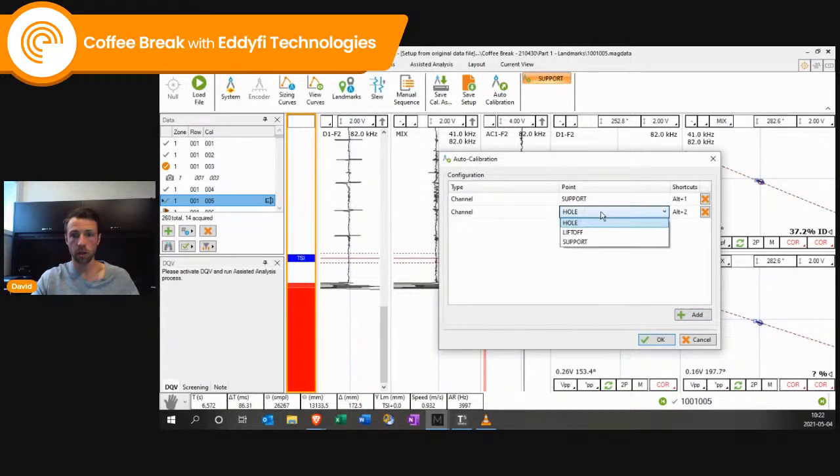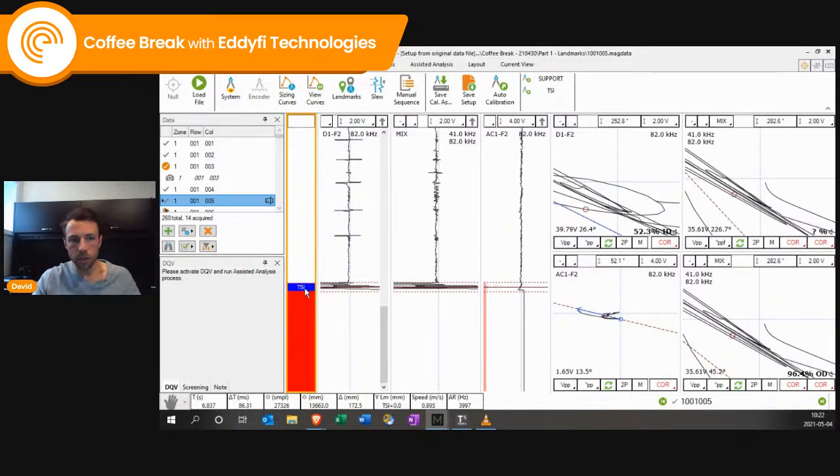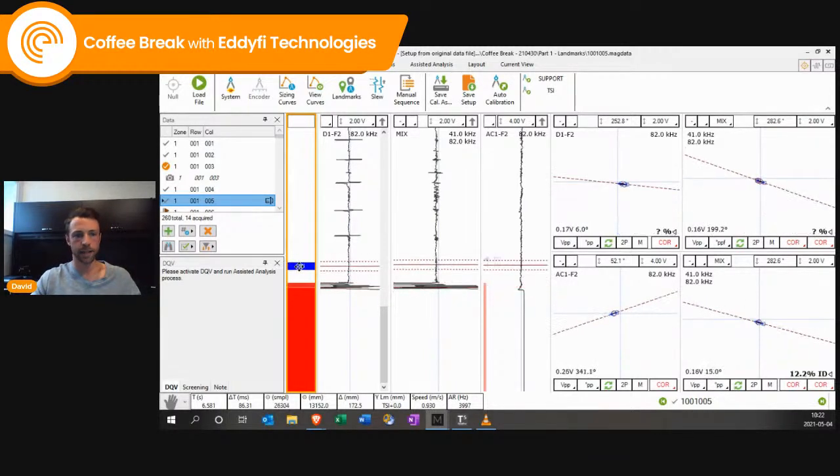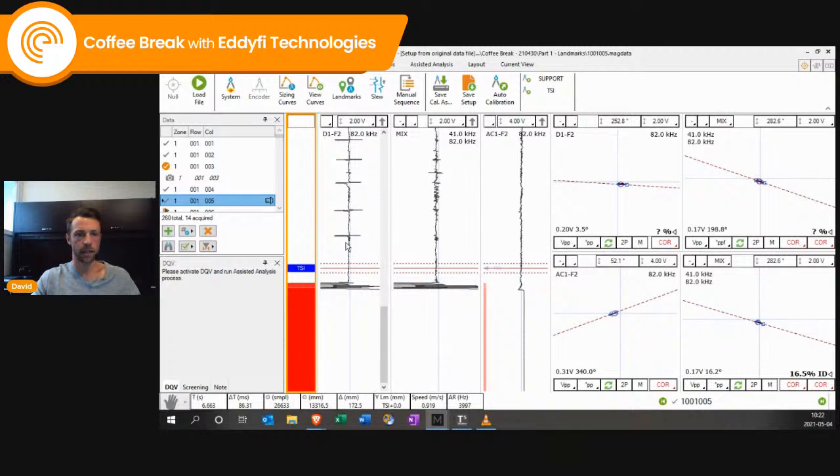Add one for landmark, then pick landmark, TSO or TSI, and I can do this very quickly. The other way around, honestly, is simply to move it. We know this tool is rule-based. It's not perfect. It does a good job, but once in a while a signal is crooked. People have slowed down in the tube sheet for whatever reason. So we can simply take them, drag and drop, and it's going to change the positioning of the defect at the same time.